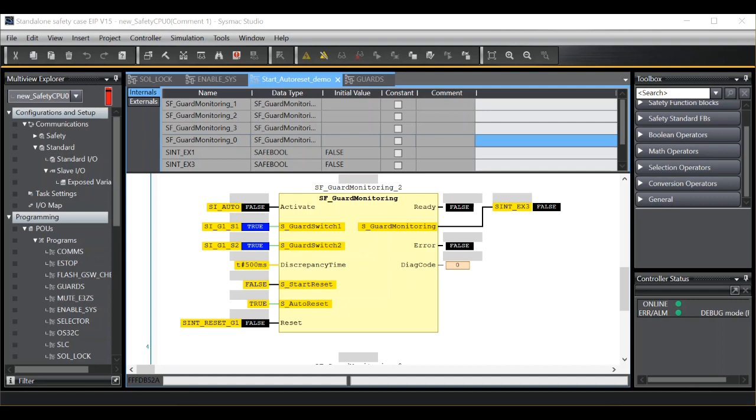So if I activate the function block, you'll see that the safety output is still in a false condition. A manual reset is required to bring the safety output on. However, now when I open and close the guard, the function block is running in an auto reset configuration.